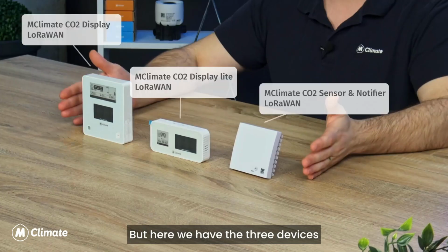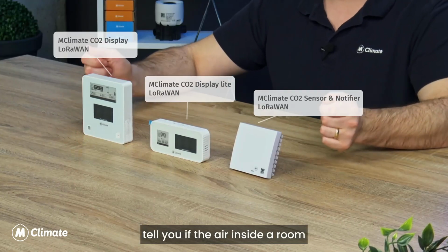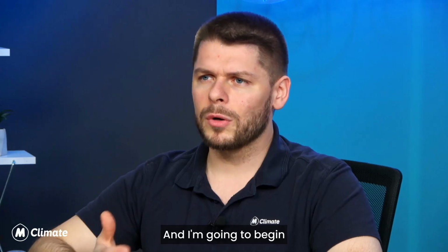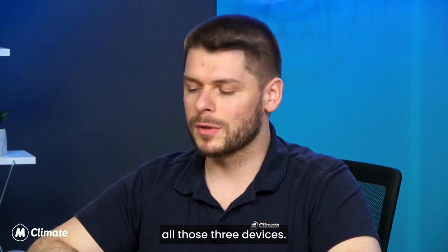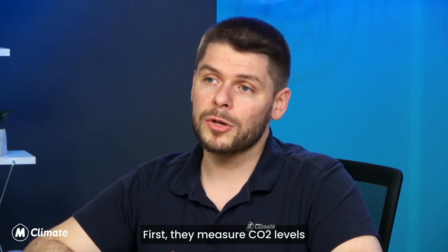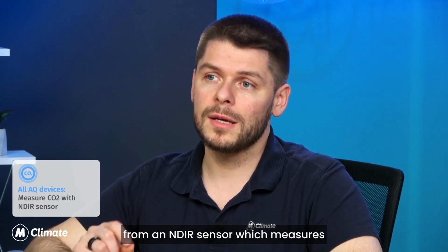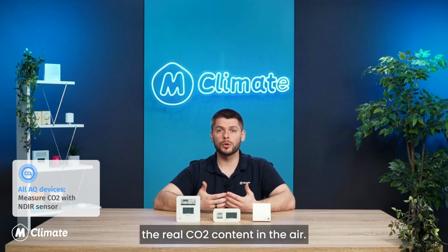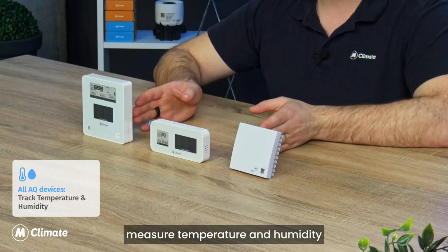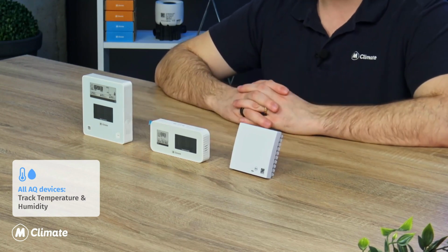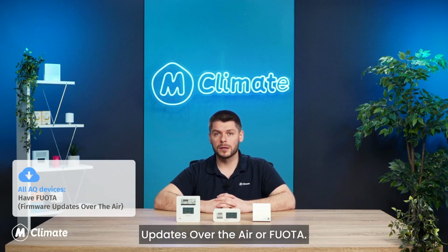Here we have the three devices that measure the CO2 levels and can tell you if the air inside a room is well ventilated or maybe over-ventilated in some cases. I'm going to begin with the similarities between all three devices. First, they measure CO2 levels with an NDIR sensor, which measures the real CO2 content in the air. Second, all of them measure temperature and humidity as well as CO2. All of them are LoRaWAN devices, and all of them have firmware updates over the air, or FUOTA.